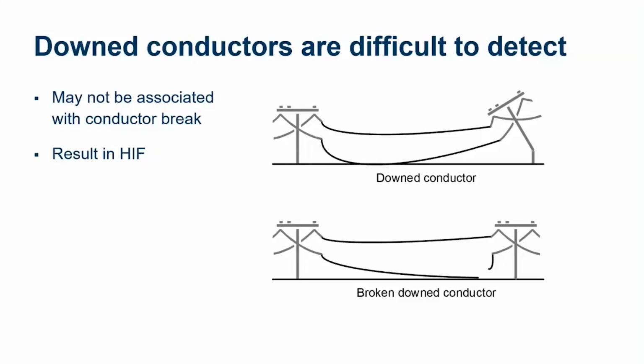Now, in this case, let's say we have maybe a tree leaning up against an overhead conductor that has not broken. For the purposes of our discussion, we're still going to refer to that as a down conductor. And in many cases, a down conductor may result in a high impedance fault. We're going to talk about high impedance faults at length, but just to be clear, when I'm mentioning a high impedance fault, I'm talking about a fault that is typically less than 100 amps of fault current. Multiple conditions will influence the amount of fault current that we see when we have a high impedance fault.